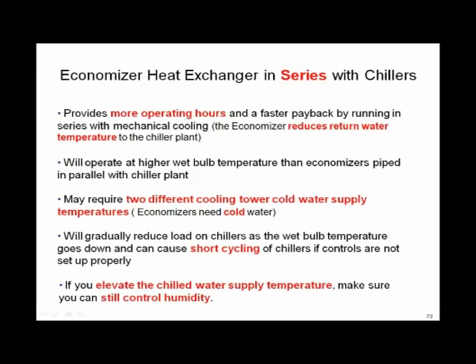So why would I want to put my water side economizer in series? Why would ASHRAE 90.1 specifically say integrate the water side economizer with the chiller so they can both run at the same time? Because by doing that, we get a lot more hours of operation. What does that mean? We get a lot more hours of higher wet bulb temperatures. We can turn it on. We can reduce the return water temperature back to the chiller plant. We can run it many thousands of hours more operating time than you can any other way.